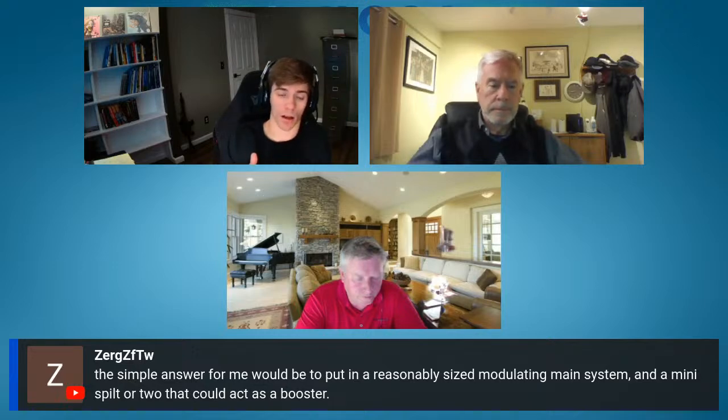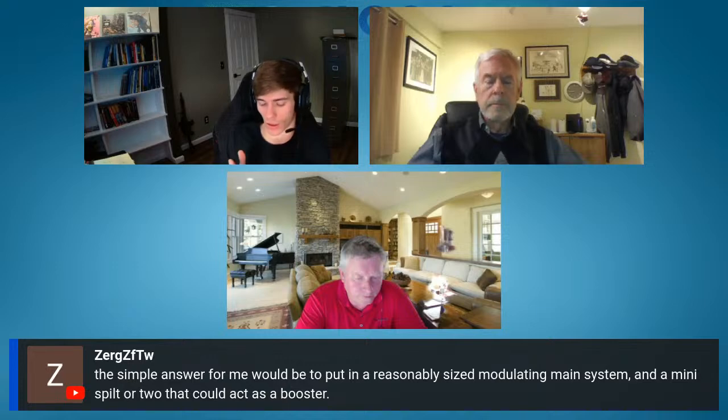Yeah, I mean, definitely if someone's requesting oversized equipment, especially if you sell the Carrier line or Trane where you have electric reheat dehumidification, that gives you a lot of buffer because those systems are going to dehumidify really well. It's just how much energy you're going to use doing reheat to make up for the difference. Obviously, an oversized system's always going to be bad.